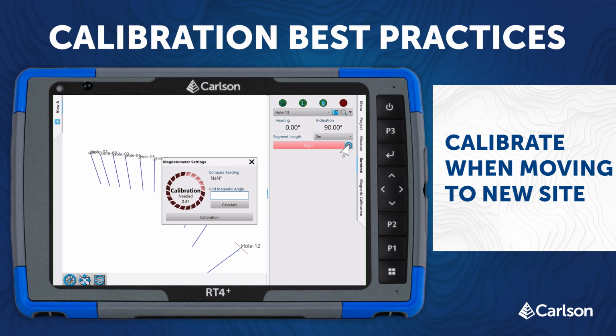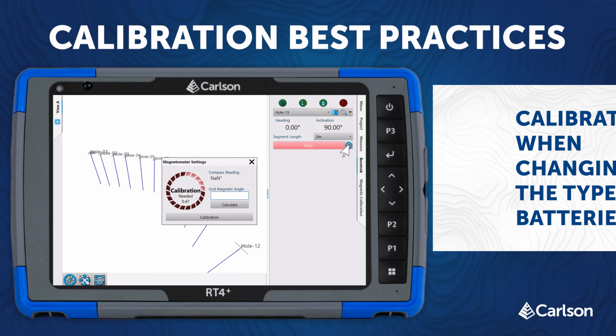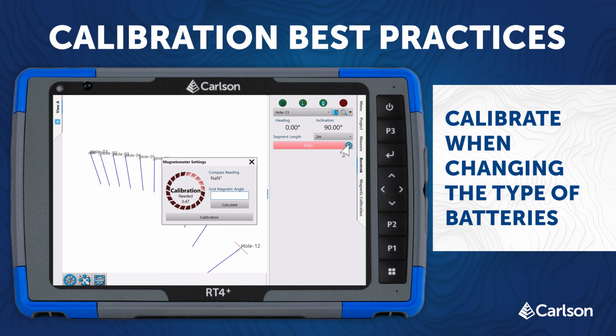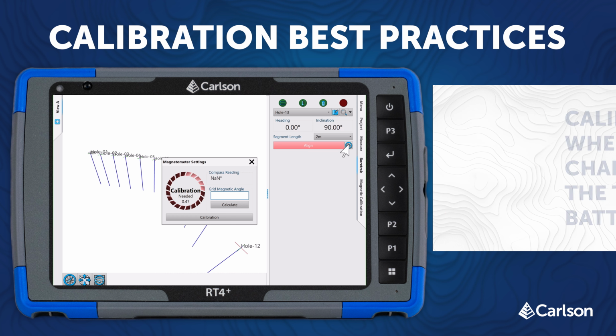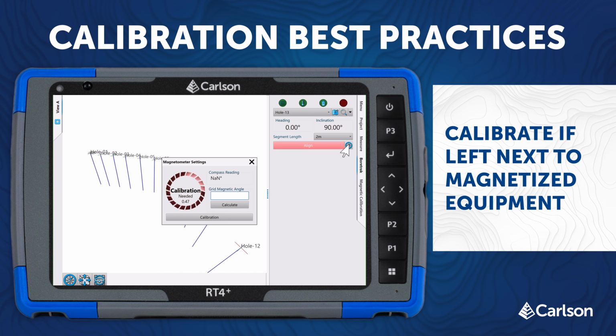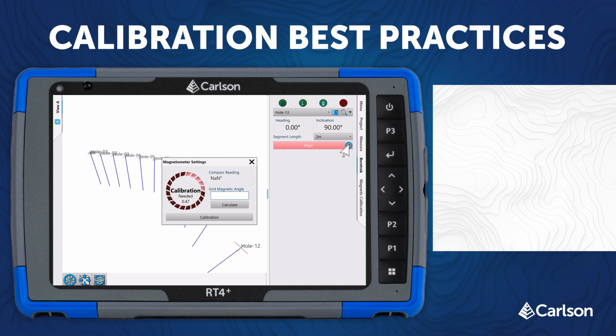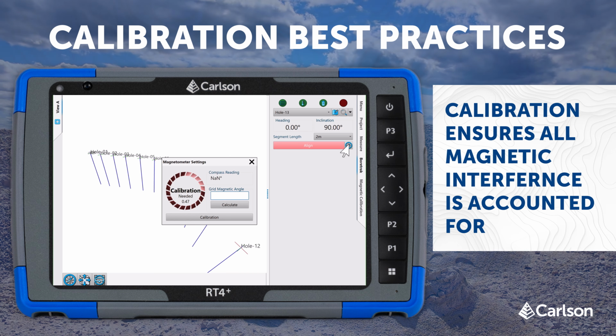Also recalibrate the compass if you move to a new site, if a different type of battery is used, or if you have left the probe stored next to something like a generator or electronic equipment which may magnetize the probe metalwork. The calibration ensures that all magnetic interference on board the Boretrak is accounted for in the output of the magnetometer.